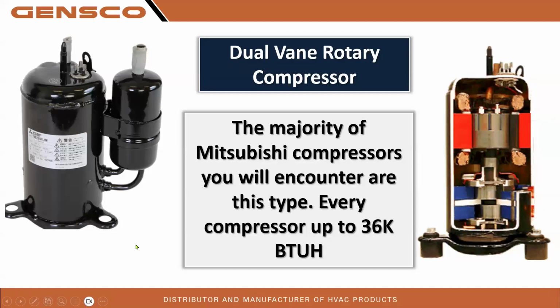The vast majority of the compressors you are going to encounter on the Mitsubishi M&P side will be the dual vane rotary compressor. You can identify this very easily by looking at the image on the left side of the screen here and seeing that there are two pipes that come out the bottom of what appears to be an accumulator and go into the side of the compressor. Those take suction gas from the suction line directly into the compression chamber, which is at the bottom of this compressor. You can see on the right-hand image a cutaway view of the same compressor with the two compression chambers at the bottom.